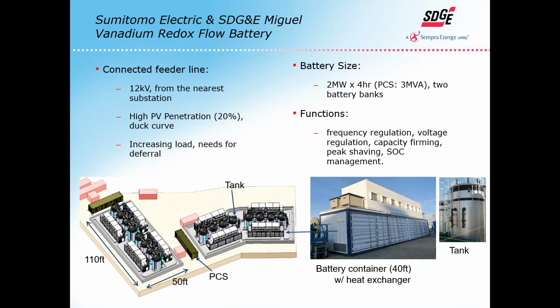As far as how we're using it right now, we have engineers scheduling the battery to dispatch, charge, and discharge. Sometimes it's just running, idling in case we need to use it, or keeping it at a particular state of charge. We're not currently doing arbitrage, which was what the question was on. But we have scheduled dispatch, and otherwise we have the ability to do four-quadrant operation. We've run tests through peak shaving and PV smoothing, but right now it's primarily for resiliency purposes, and then scheduled discharge if needed.